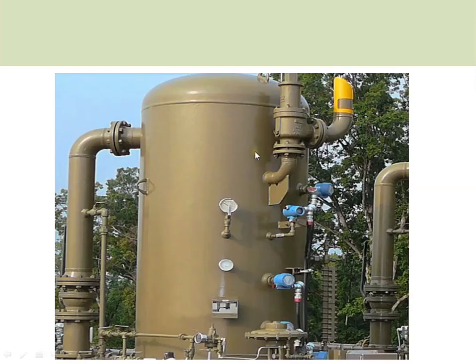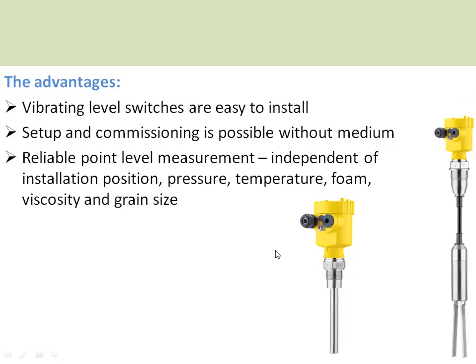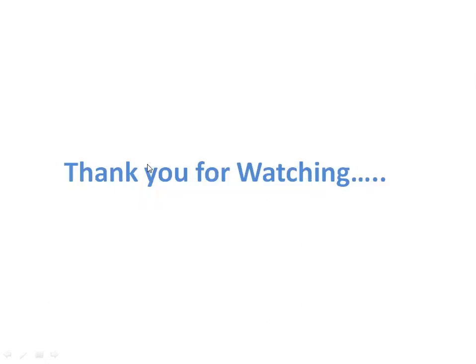These are typical examples of where vibrating level switches are connected to a tank for controlling or monitoring applications. The advantages of this vibrating type level switch are: it is very easy to install, setup and commissioning is possible without the medium present, and it is independent of pressure, temperature, foam, viscosity, grain size, and installation position. It is commonly used for point level control applications.